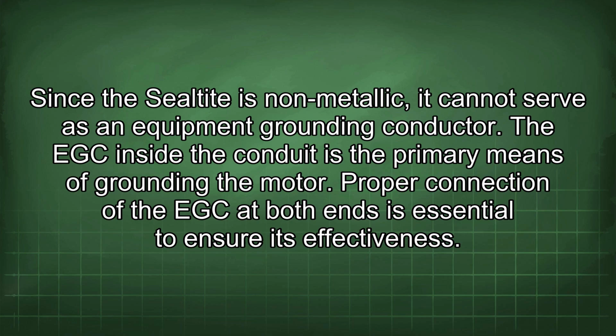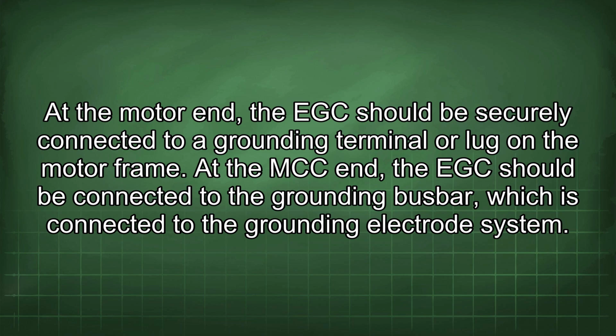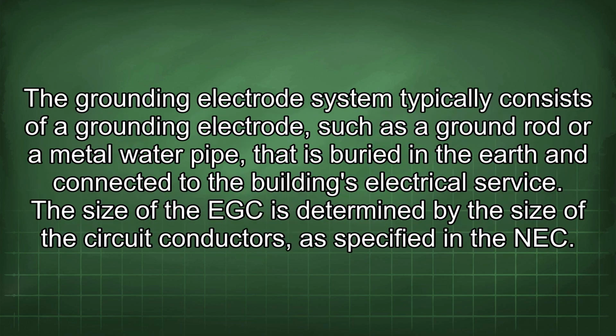Since the Sealtite is non-metallic, it cannot serve as an equipment grounding conductor. The EGC inside the conduit is the primary means of grounding the motor. Proper connection of the EGC at both ends is essential to ensure its effectiveness. At the motor end, the EGC should be securely connected to a grounding terminal or lug on the motor frame. At the MCC end, the EGC should be connected to the grounding busbar, which is connected to the grounding electrode system. The grounding electrode system typically consists of a grounding electrode, such as a ground rod or a metal water pipe, that is buried in the earth and connected to the building's electrical service.